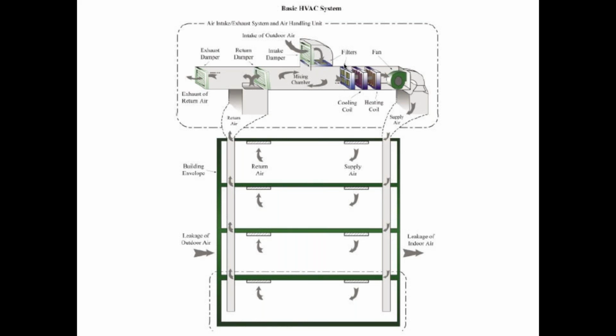If you pop up one of these ceiling tiles and look in there, you can see almost the whole floor. It's all open up there. There's an air handler located somewhere on this floor, though technically there isn't, but I'll talk about that later. There are actually four giant air handlers for the whole building, but in most buildings like this, there's an air handler for either the whole floor or part of the floor, and that ceiling area is open and connected, either by a duct or an opening, to the room where the air handler and the fan are located, and that fan is sucking air from that ceiling area.